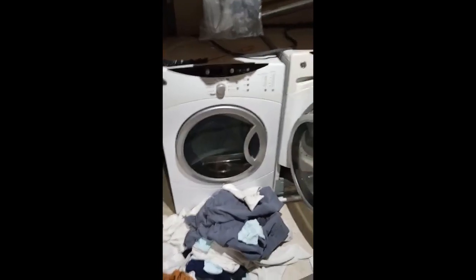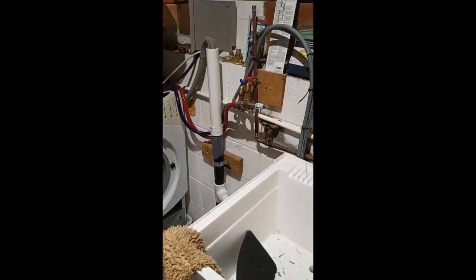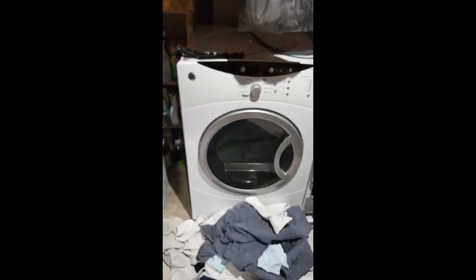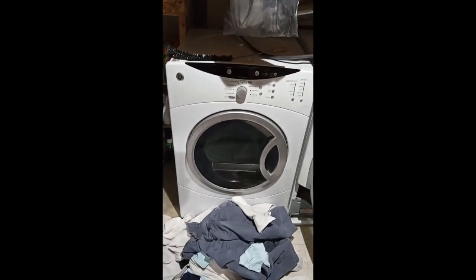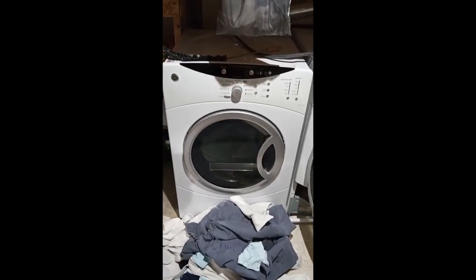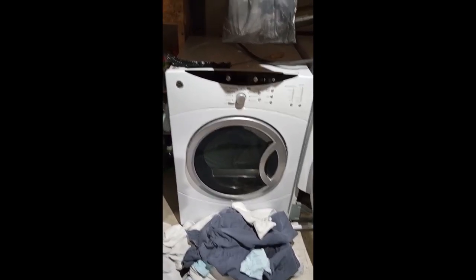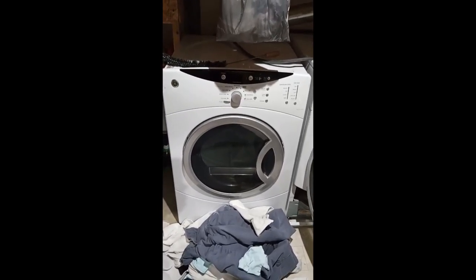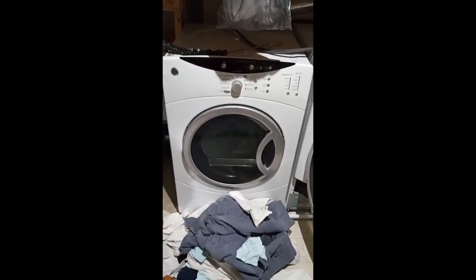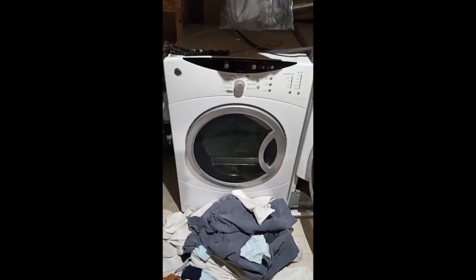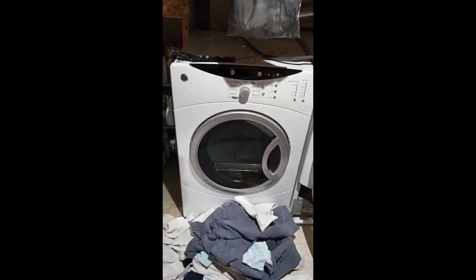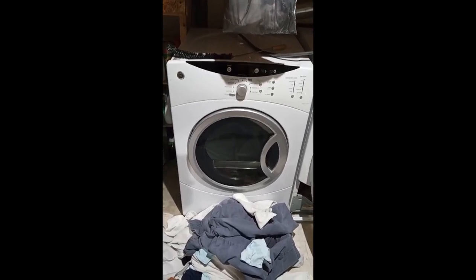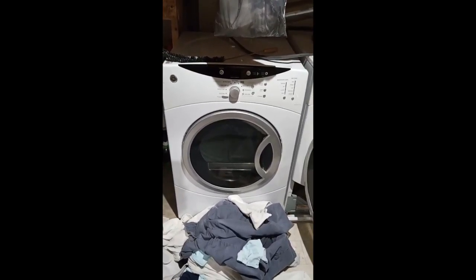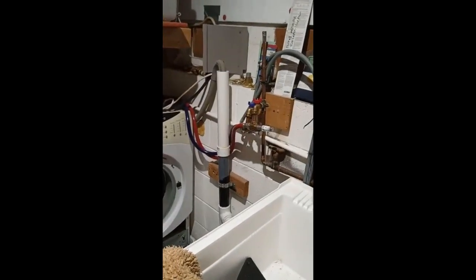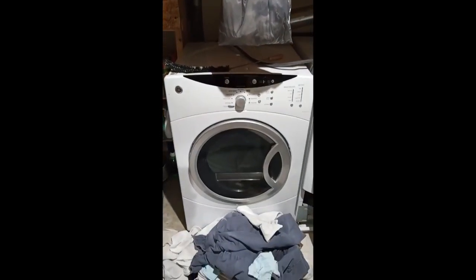This laundry area under electrical code is a wet area. On the back of this unit, there's clearly called out a ground connection which is required. If it's not there, somebody's going to die, because a sagged heating element is very likely in an old dryer. Common failure. If that happens and the cabinet of that machine is not grounded and that heating element sags and somebody comes down here and touches that cabinet, they're dead. They're dead, Jim.